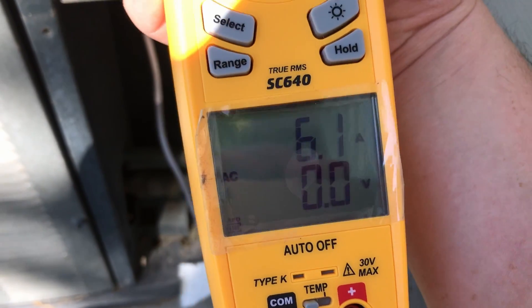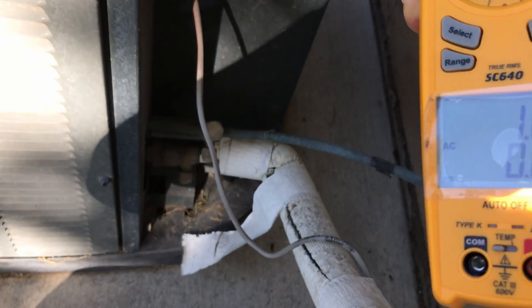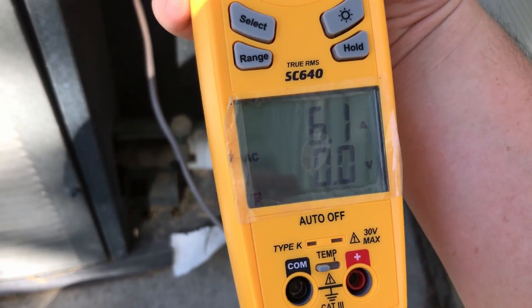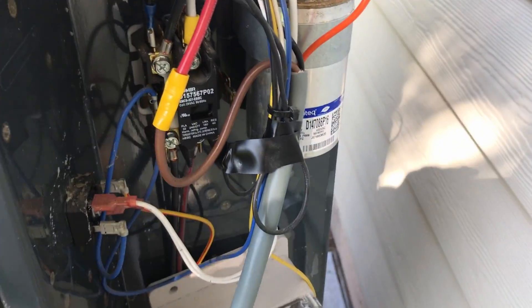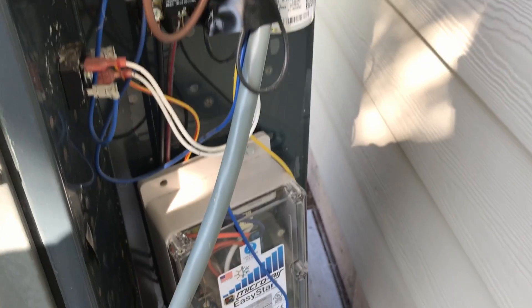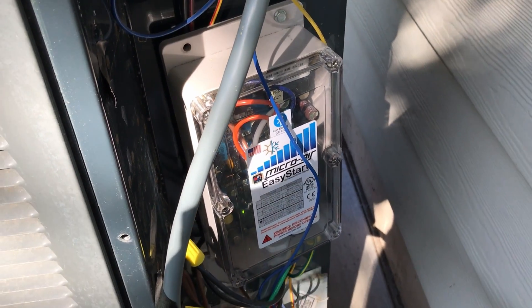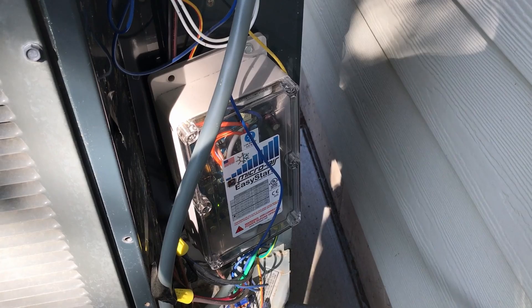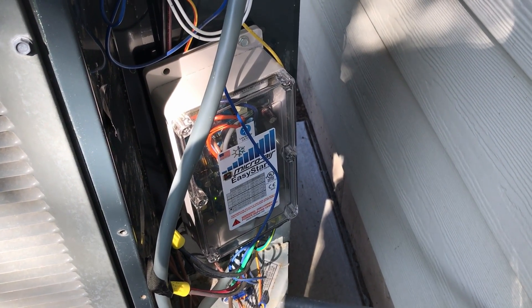And once again, the main wire down here — the black one is 6.1, 6.0, and the red one is 6.1 as well — same on both of those wires. I didn't notice hardly any difference on the wires coming out of the top there. So if it does consume any power, it's very, very minimal, because we're hardly seeing any kind of difference before versus after the Easy Start. Hopefully that is helpful and provides further information for all of you who were curious about that.